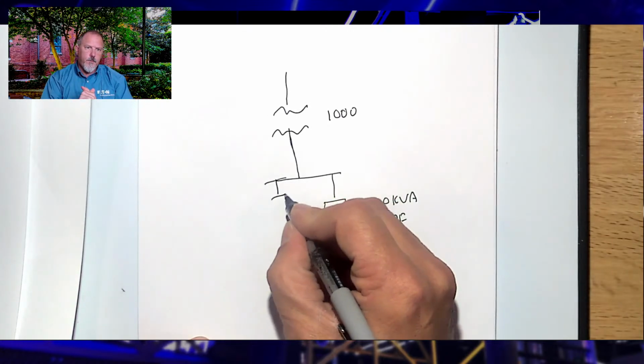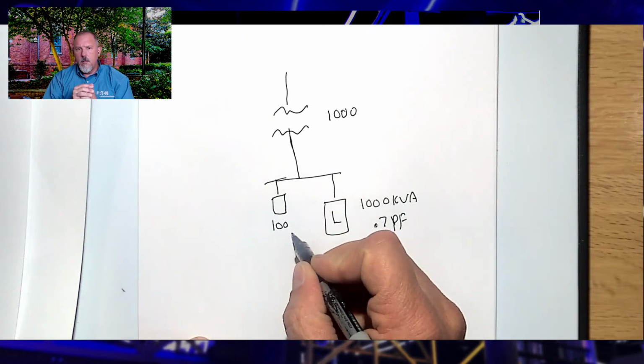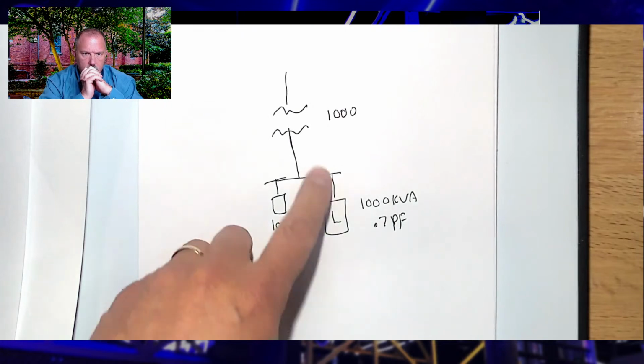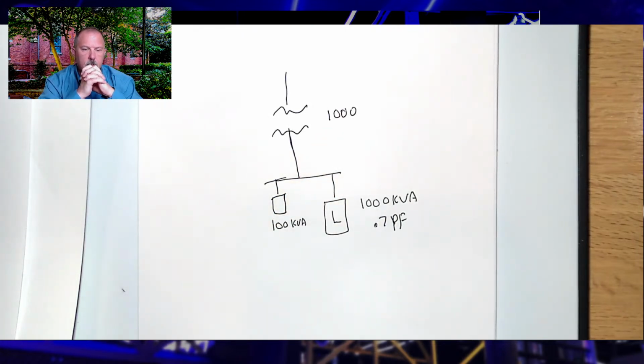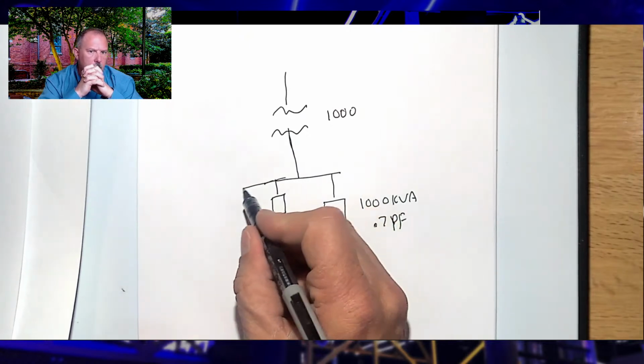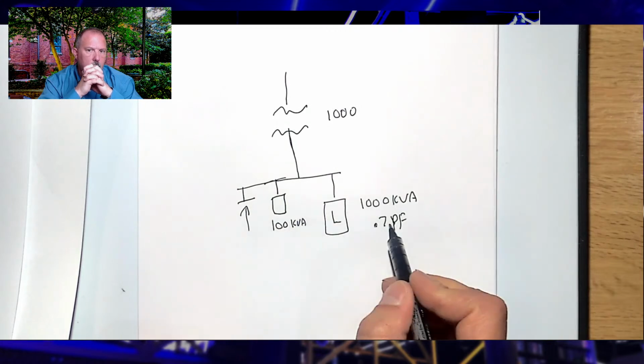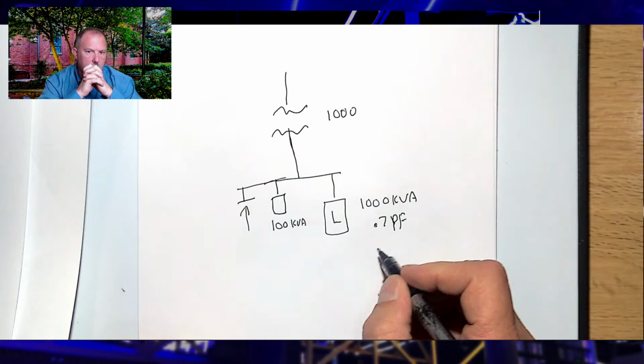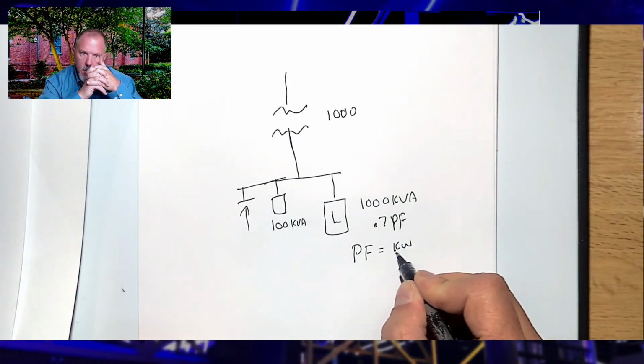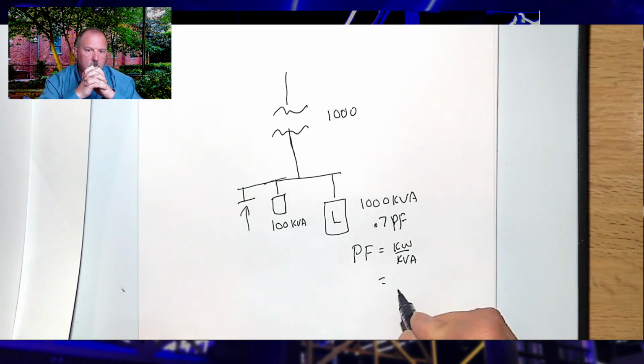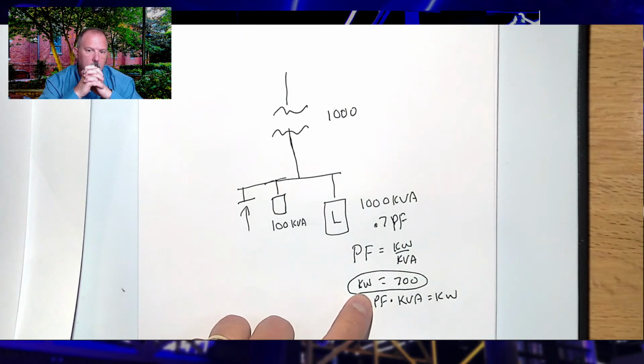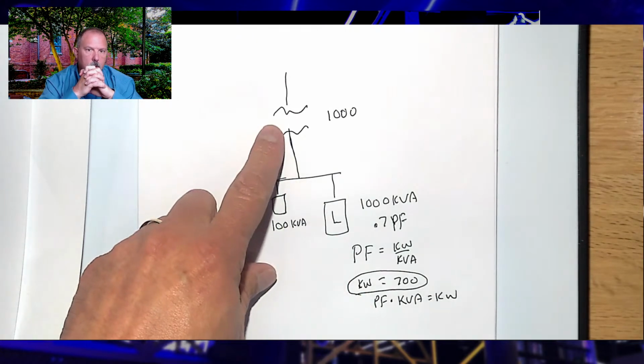If I wanted to put another load on here, let's say another 100 kVA, I can't do it because I'm going to overload that transformer. So the utility says, okay, if you put in a capacitor and size it to compensate for that low power factor, theoretically... What's the power factor? Power factor equals kilowatts over kVA, simply. So power factor times kVA equals kilowatts, so your kilowatts equal 700. You're really only paying them for 700 kilowatts, but you're using a capacity of 1,000 kVA.